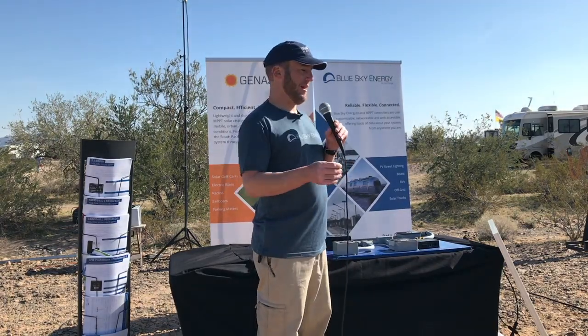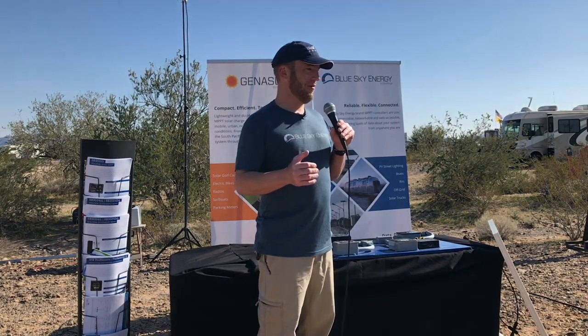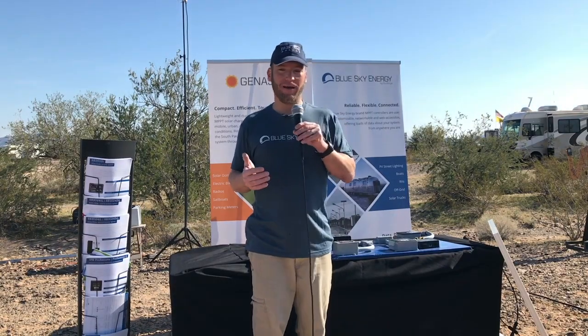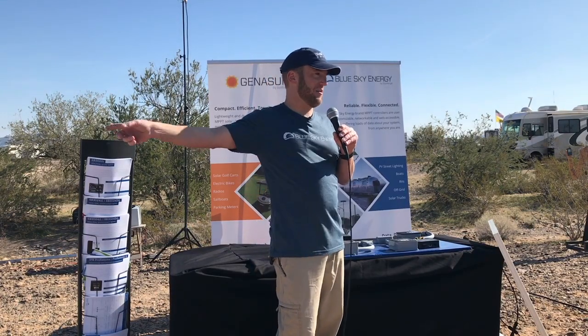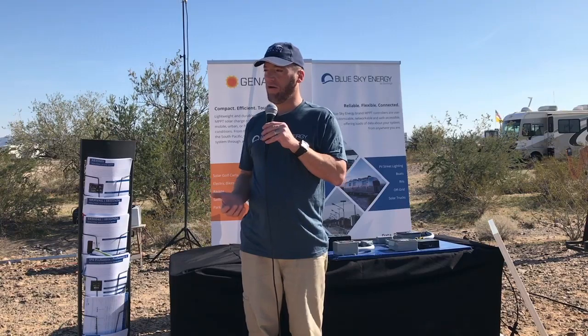Speaking with the owner or chief engineer, he says connecting the solar panel first is better because if you accidentally short your solar panel's inputs while the controller is energized, you're going to kill your controller, and even a fuse won't save it on the panel side. So for wiring safety, it's a little safer not to cross the streams: connect your solar first, then your battery. If you spark your battery wires, that spark goes to the battery and blows the battery fuse. If you spark your solar wires while connected to an energized controller, it's going to kill your charge controller.